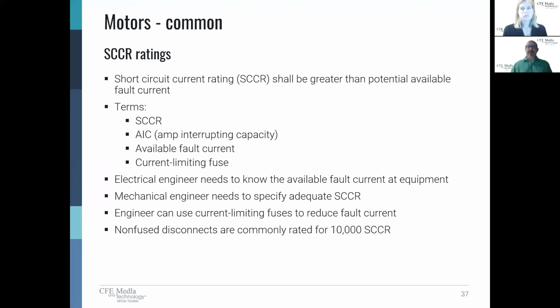Now, for every piece of component, we need some sort of a disconnect. We have some electrical interface to motors or pumps or things like that. What you should know is that there's an SCCR, short circuit current rating, and that is how many amps, typically in the thousands, that component can handle before it fails. Now, you might say, well, I don't need 10,000 amps to run that equipment. I just need 10. Well, that's actually not where the SCCR rating is derived from.